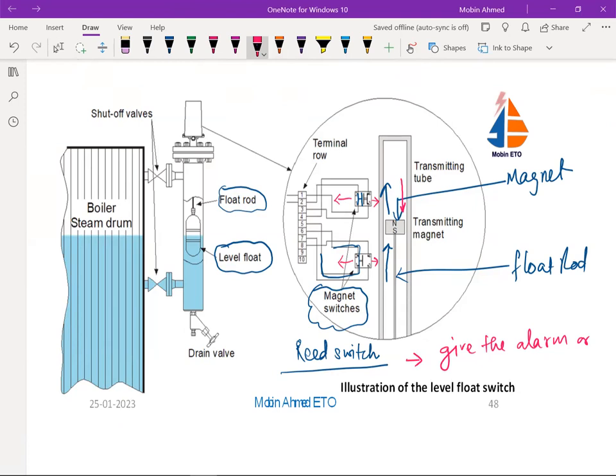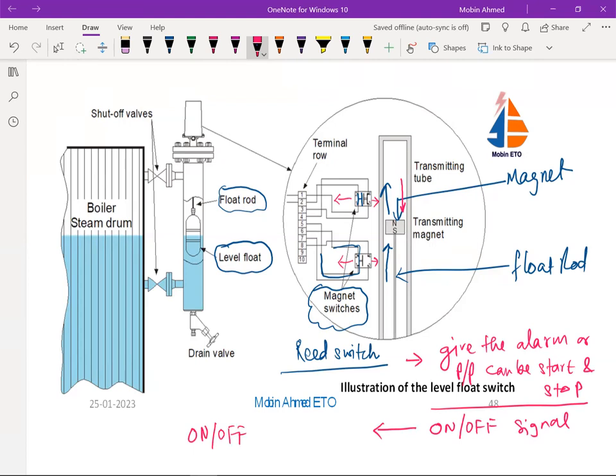So here, if the number of switches we are going to put here, it is going to give the alarm or the pump can be started and stopped. Start and stop. So this is how it is going to work. So this is the float switch. This is how it is going to work. So now again, this is going to give the on and off signal. Wherever we are having the on, this is not a continuous one. So it is going to give a discrete signal or the on off signal. That is what we know. And that's why it is going to be used for the on off control.